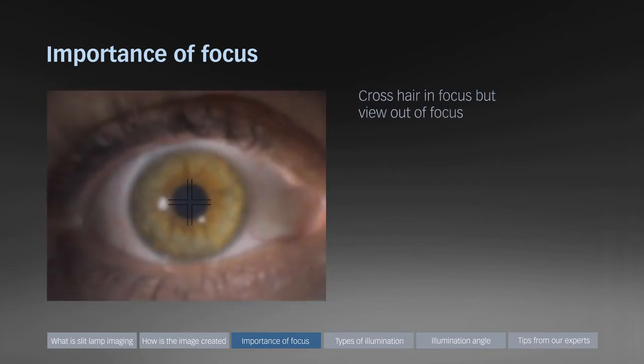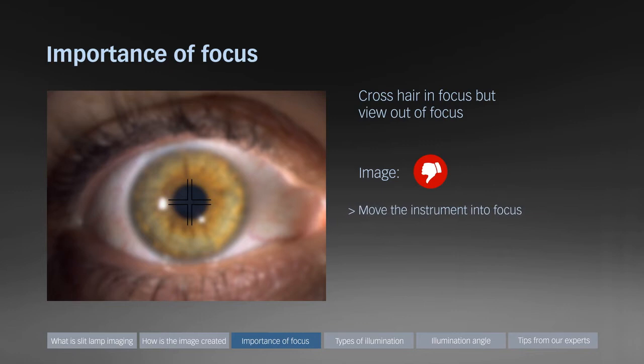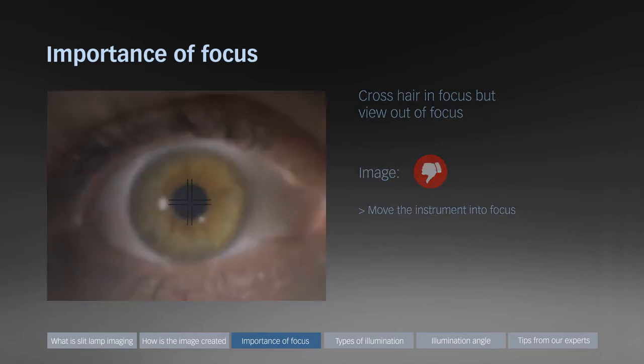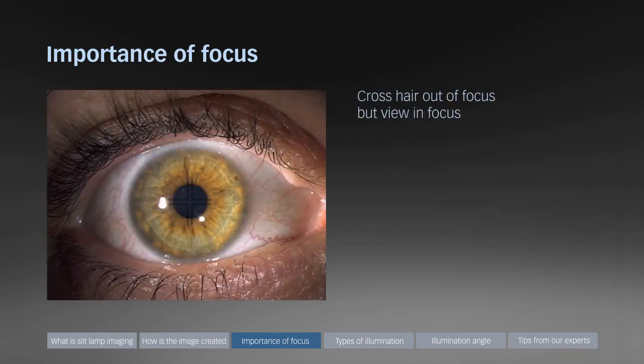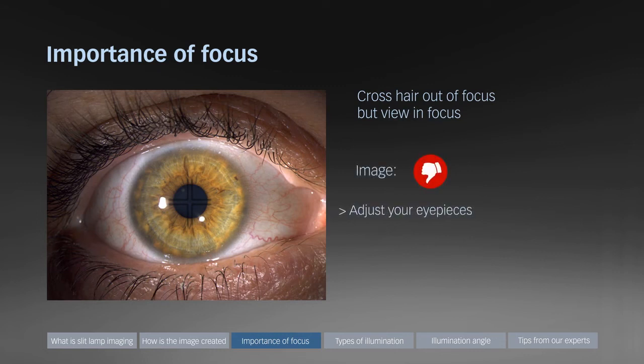If by looking through the eyepieces the crosshair is in focus but the view is out of focus, you need to move the slit lamp into focus. If by looking through the eyepieces the crosshair is out of focus but the view is in focus, you need to adjust your eyepieces.